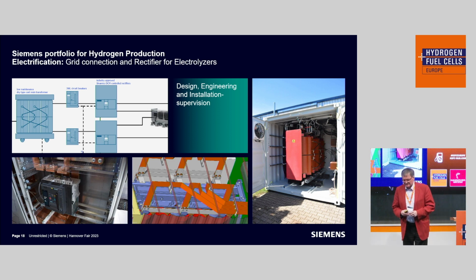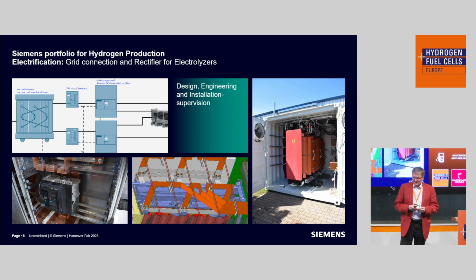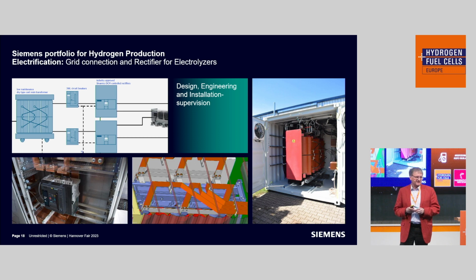This is also available from us. We designed all the transformers and circuit breakers, the medium voltage and low voltage switchgear that you need, because we are talking about voltages of about 600 volts and 6,000 amps. We designed the containers. We have the DC master product that controls the power. We did all this, and it's very space consuming. Usually the buildings that host these parts are larger than the electrolyzer building itself.